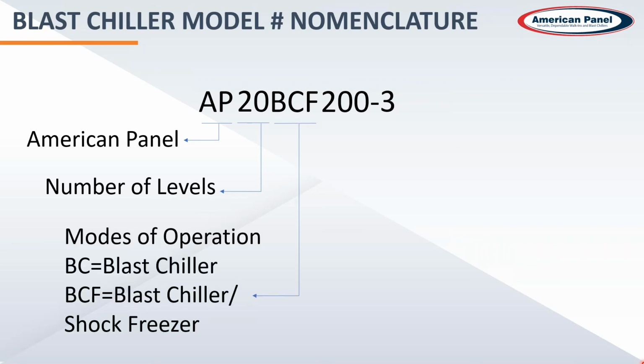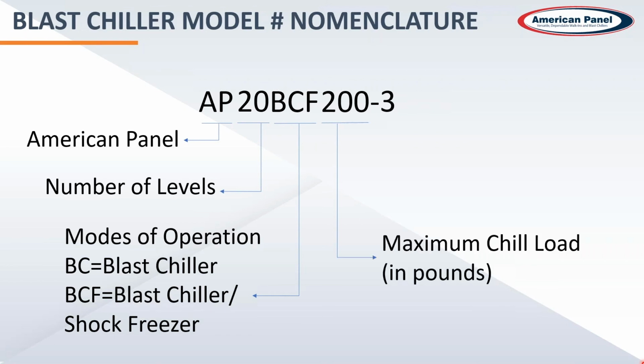BCF, this is going to be the modes of operation. If it's just a BC, then it's a blast chill only. If it's a BCF, it's a blast chiller and a shock freezer. The next is the number of pounds. On here, the 200 pounds per cycle. And the last number is going to be the electrical configuration. This is a -3, so this is a 208 3-phase. A little bit more on that here in the following slide.